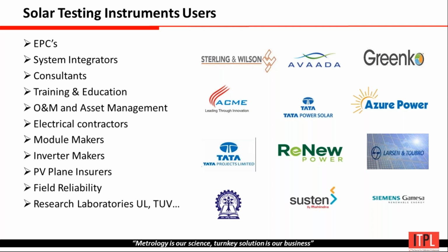If you tell your supplier the solar panel isn't performing as expected, they might ask you for the data, and you'll do the IV curve, with the software extrapolating it to STC, and you can give that same report to the module manufacturer. They might then bring the same kind of equipment to your site, or send their engineers to test with the same equipment, and they will clearly see if there is an issue.